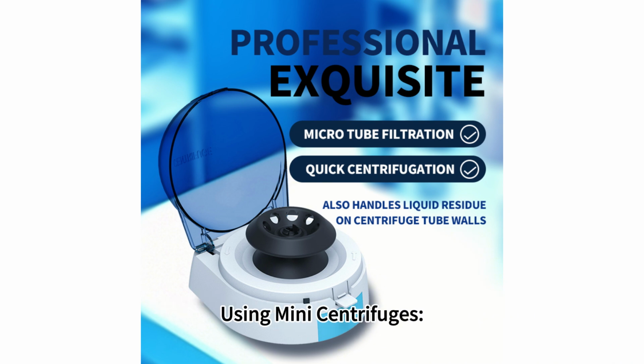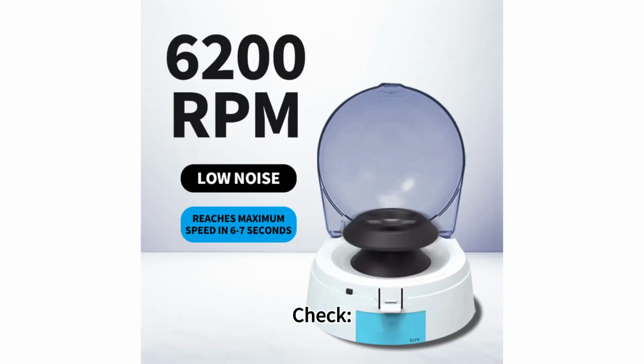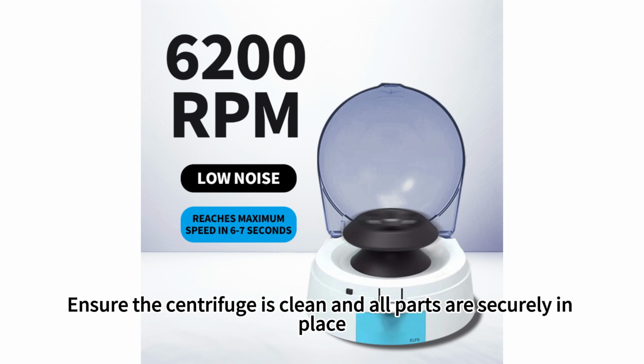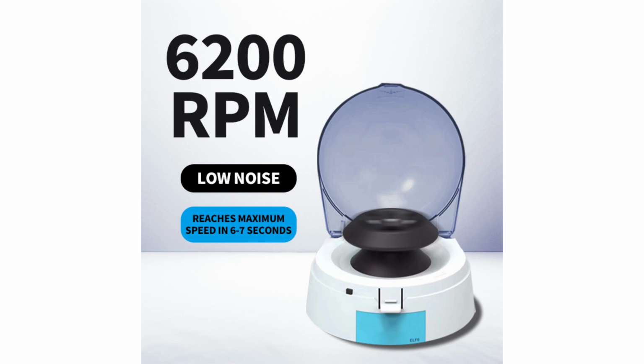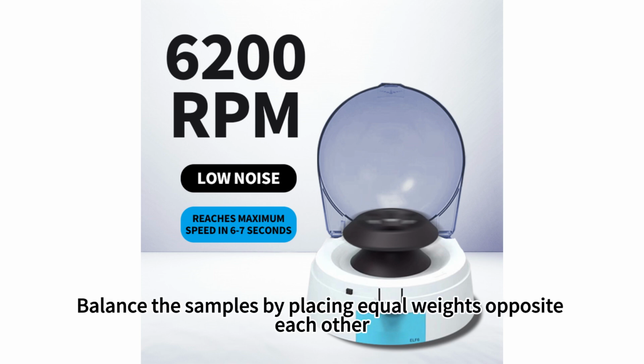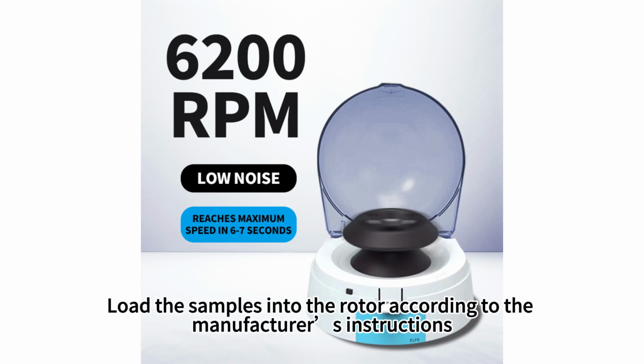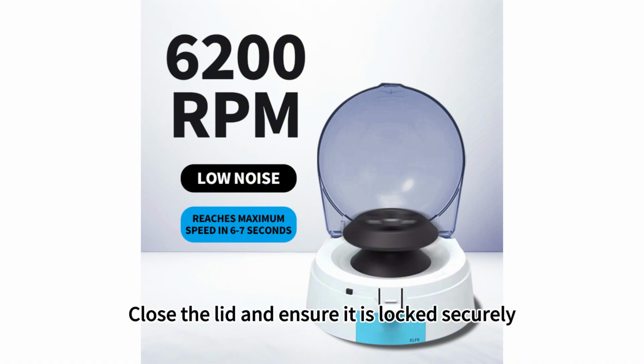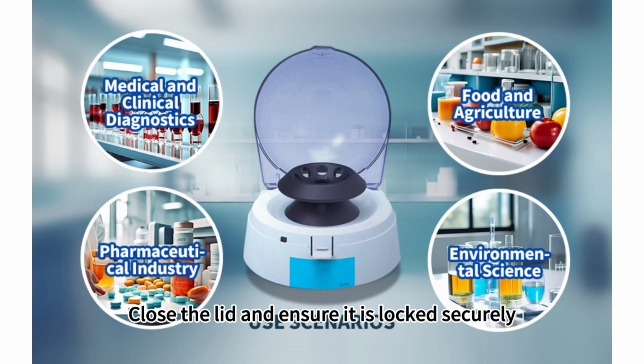Using mini centrifuges. Preparation. Check. Ensure the centrifuge is clean and all parts are securely in place. Balance the samples by placing equal weights opposite each other. Loading. Place. Load the samples into the rotor according to the manufacturer's instructions. Secure. Close the lid and ensure it is locked securely.